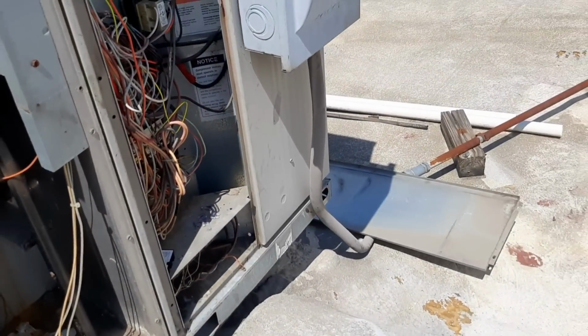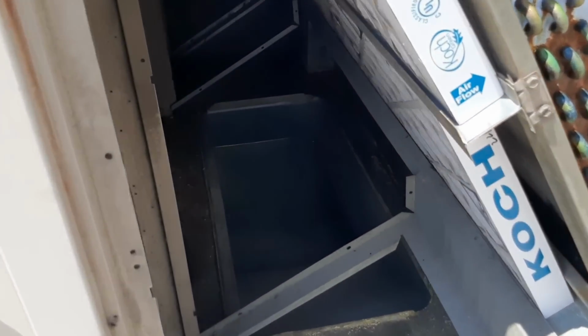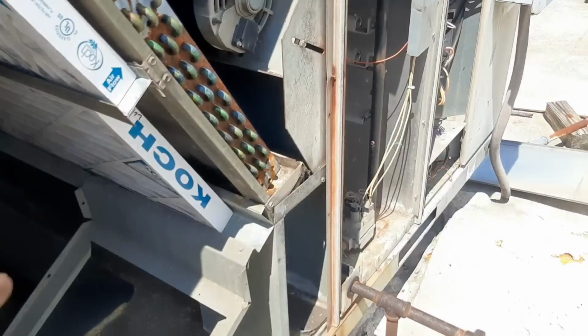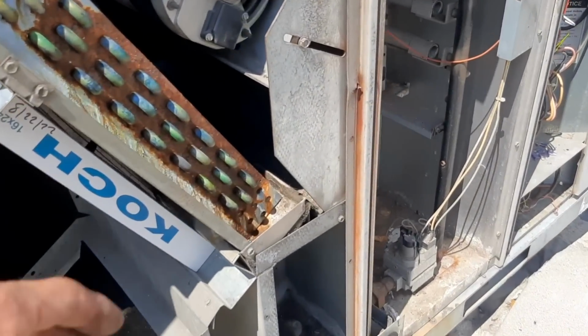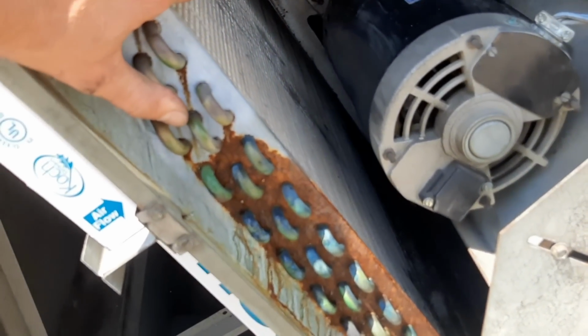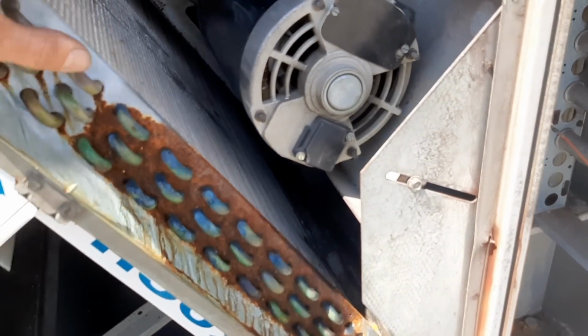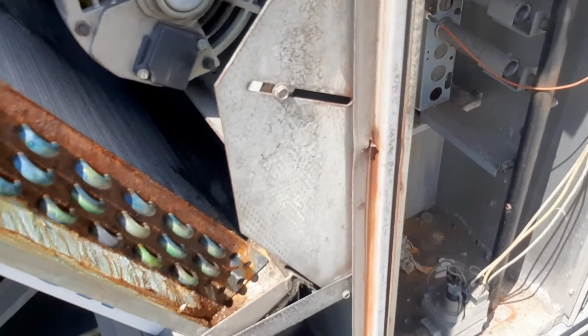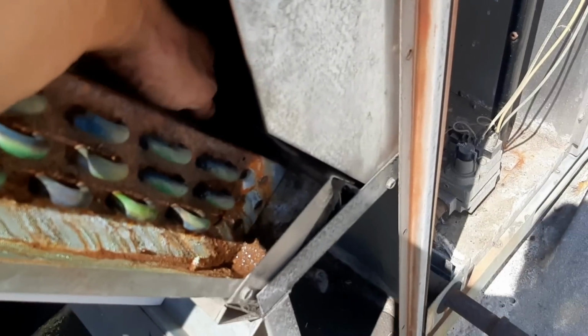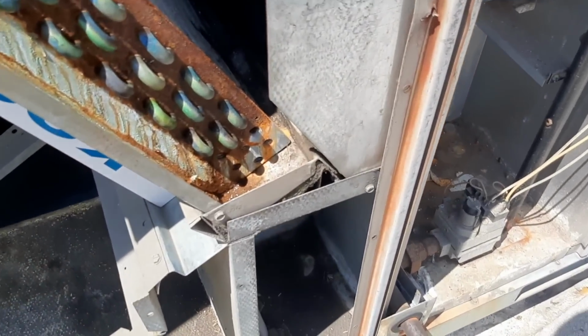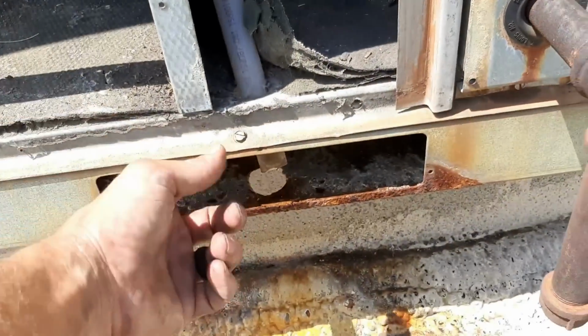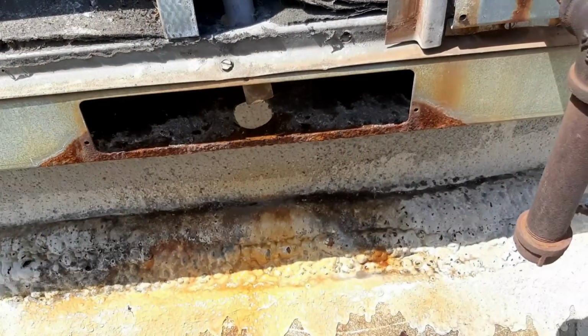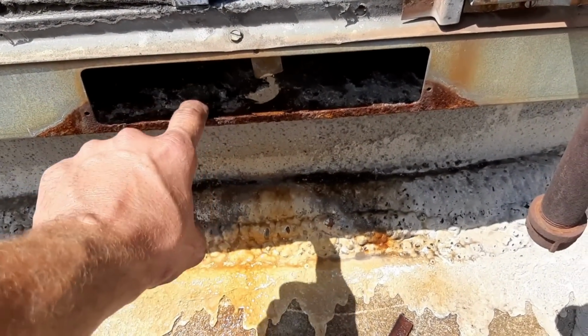So we're gonna kick it back on, get a temp drop with the new filters. It was running a little high when I got back, it was putting out about 57 degree air, so we might still have airflow issues, but not terribly concerned about anything else. You can see they got your drain right there - they're just draining right into the rusted out curb.